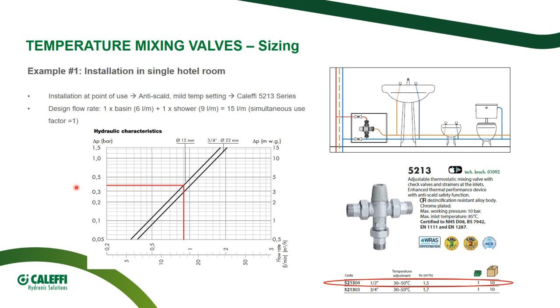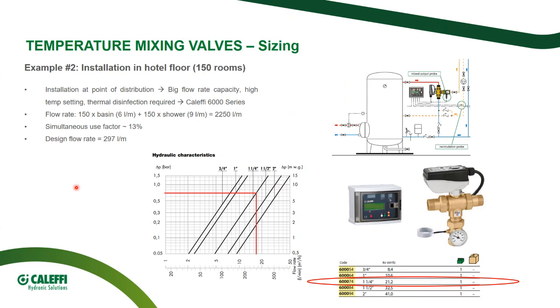In the same way, if we want to consider the installation of a digital mixing valve serving the whole hotel, for instance, we suppose 150 rooms. In this case, we install the device at the point of distribution. It is a hotel, so I need big flow rate capacity, of course. I need a higher temperature setting because I have to do the first temperature reduction. And I need to be able to perform the thermal disinfection, so I move towards the Caleffi 6000 series, the electronic mixing valve.